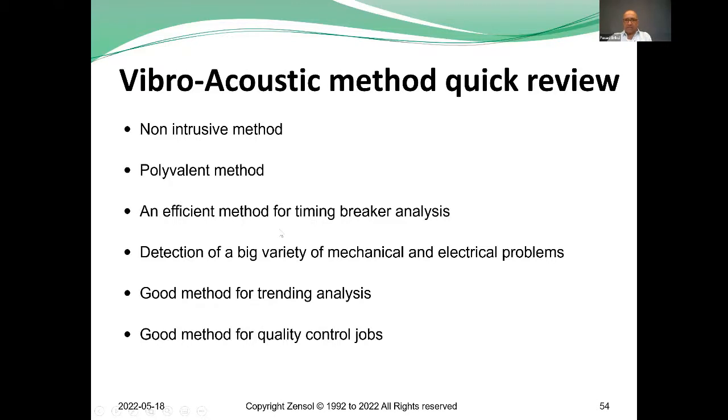It's very easy. It could detect a big variety of mechanical and electrical problems. Also, I didn't present some electrical problems here. And it's a very good method for trending analysis, because if you always get the same impact and the same noise from test to test, you just do nothing and do not open. And it's a very good method for quality control jobs.